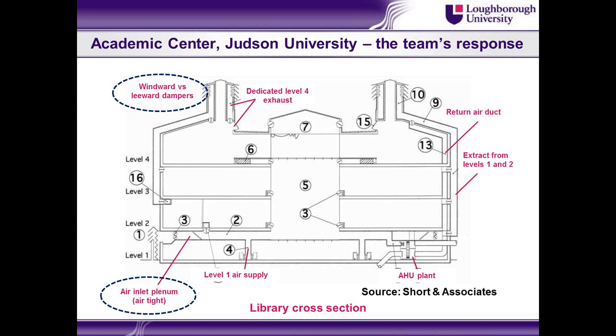And down here in the plenum, it was important that the dampers were airtight because, as I say, small driving forces, so when we're in natural ventilation mode, we've got very large openings. So what you want to make sure of is when you switch over from passive mode to mechanical mode, when you're filling this plenum up with mechanically cooled air, you don't want that leaking out through the dampers. So very important that that's airtight at that location there. So these are just some of the elements of the design and commissioning that were certainly different to business as usual.